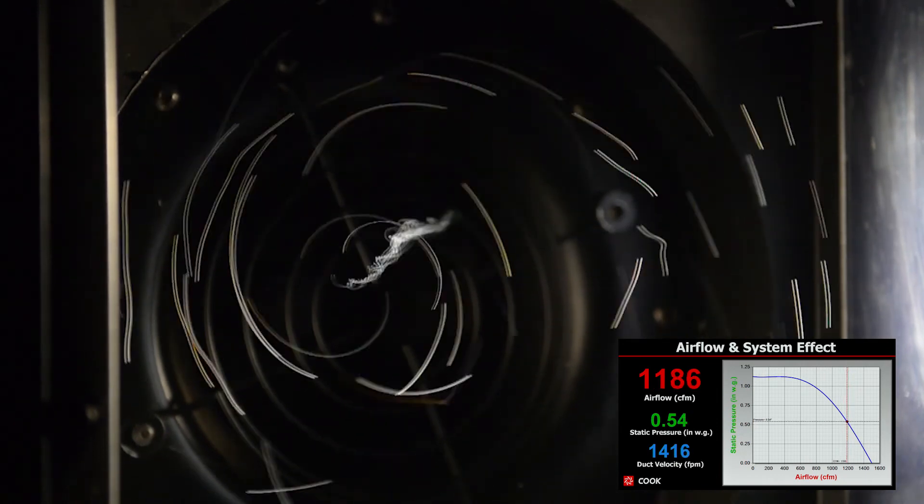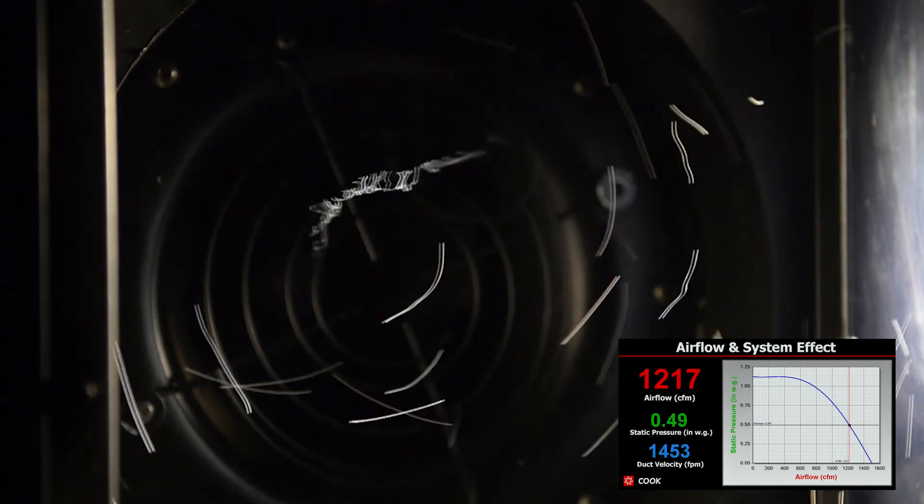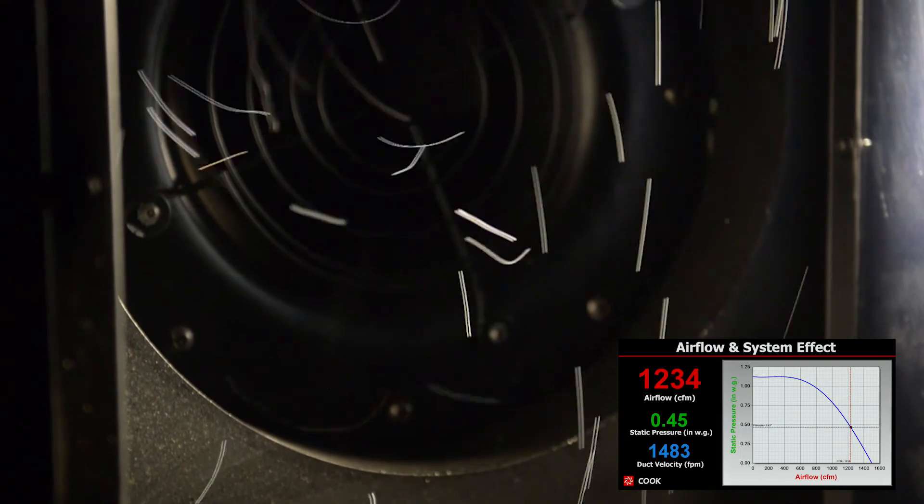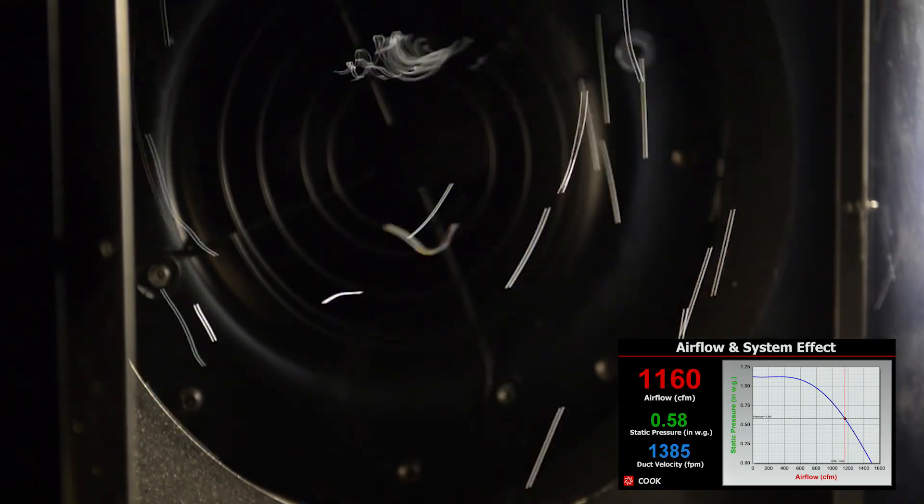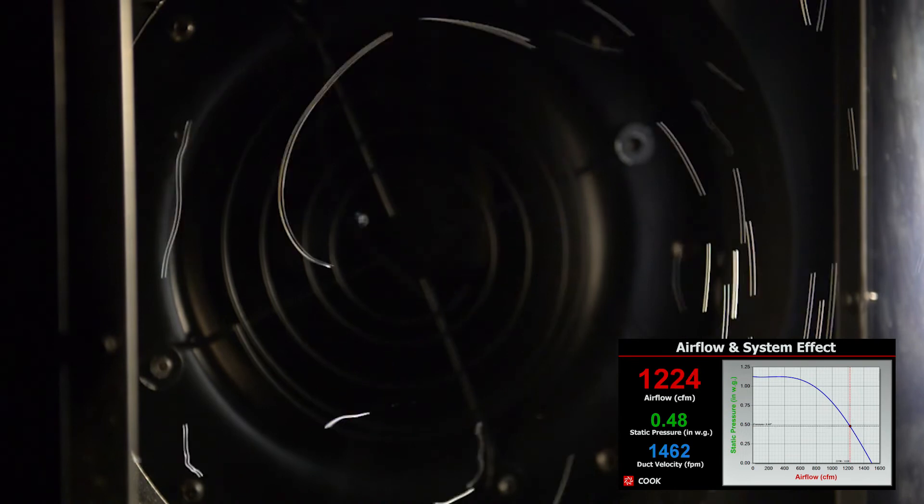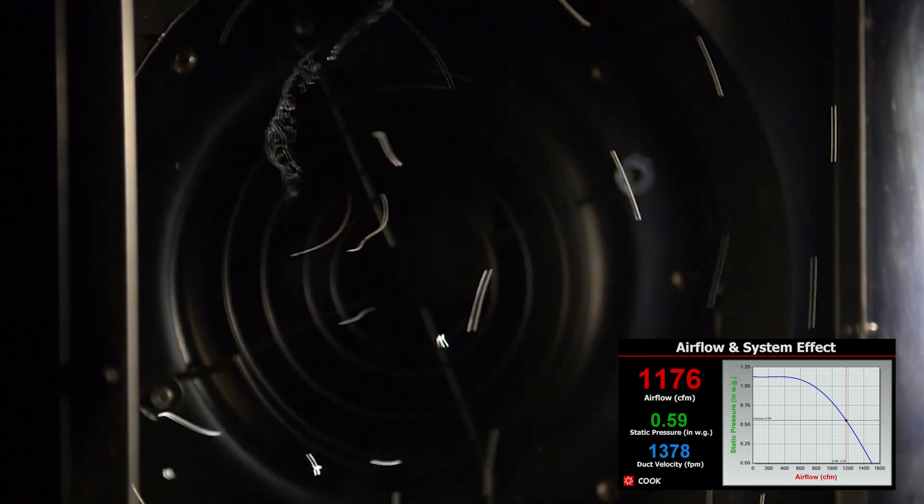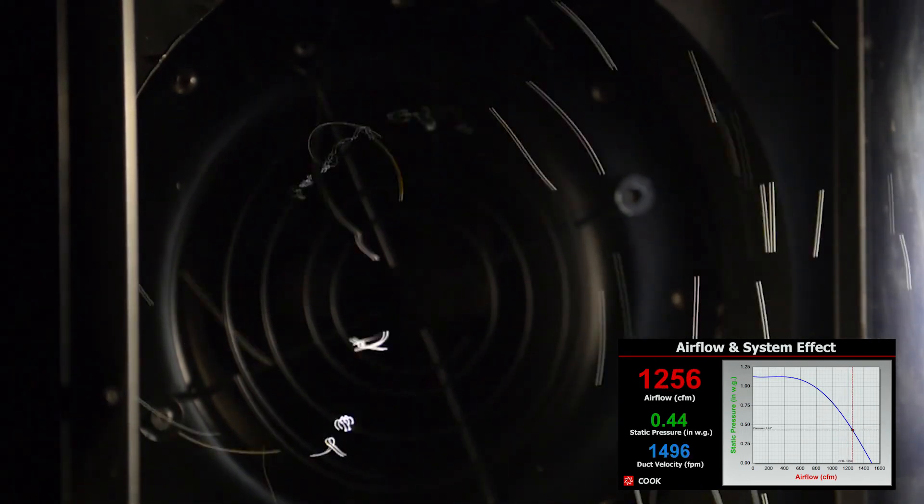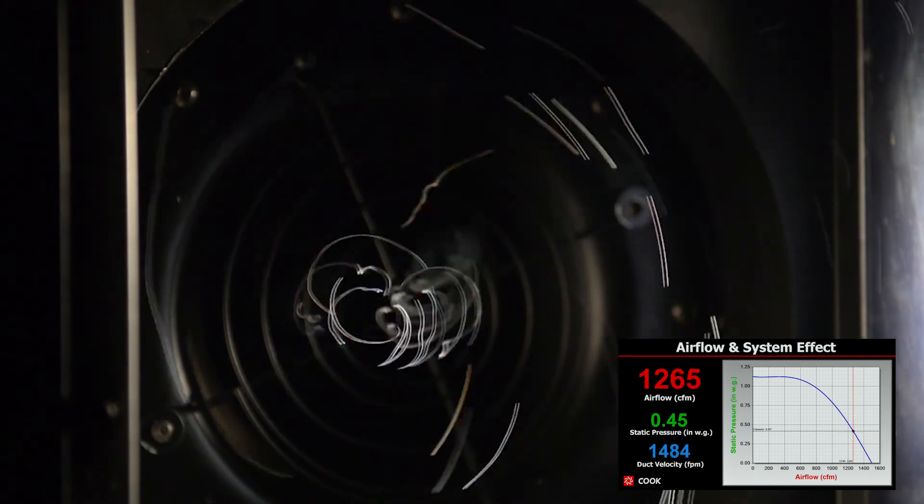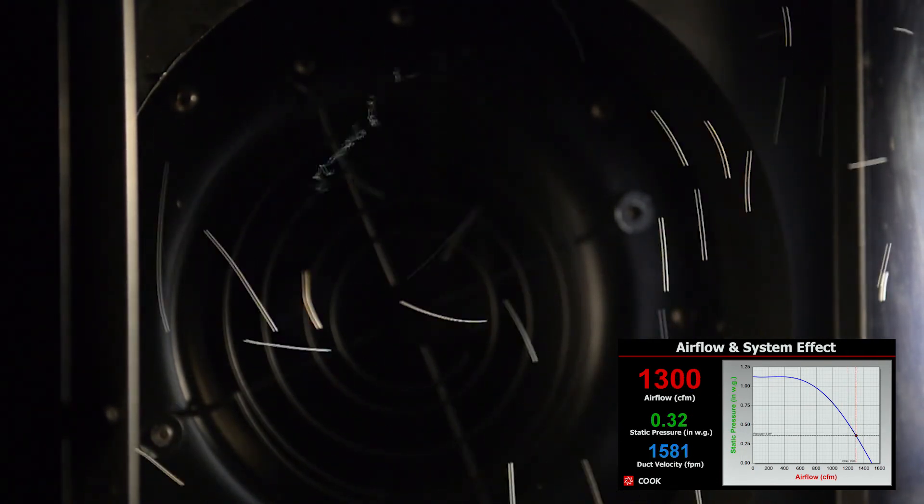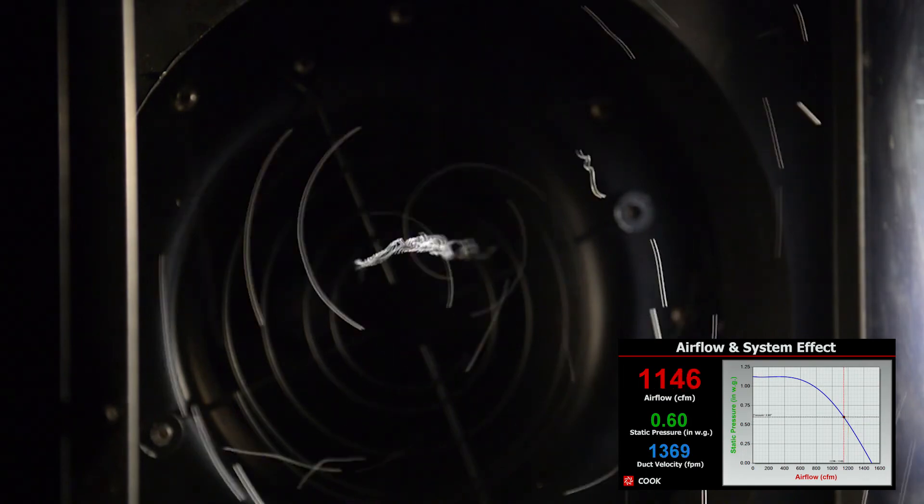We can also see the pressure loss swinging wildly with the changing airflow patterns. When the airflow is spinning in the direction of the fan rotation, the pressure drops, and when it is rotating opposite the fan, the pressure rises. Surging unstable airflow with a wildly varying pressure is not ideal. So what can we do to fix the problem?